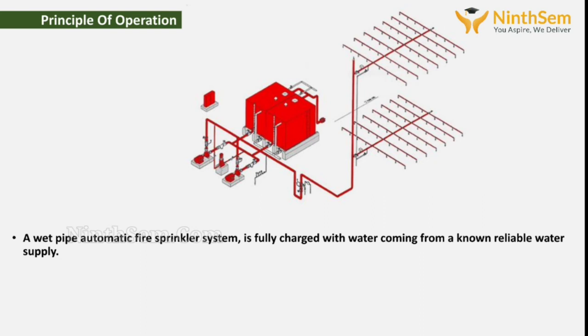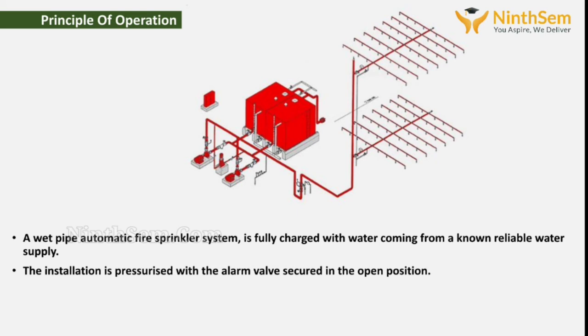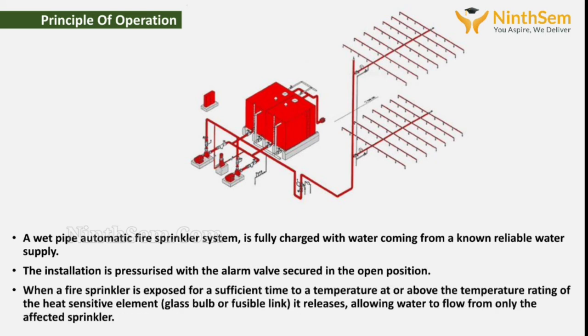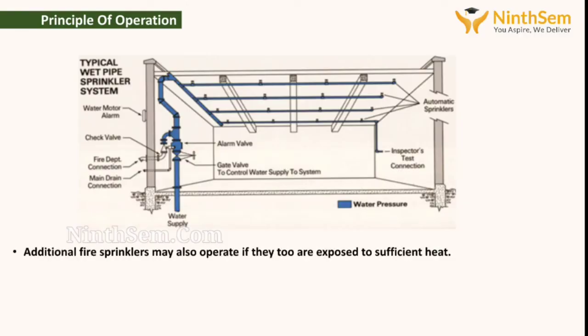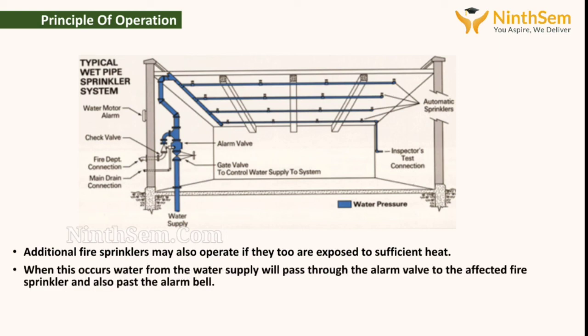So normally a wet pipe automatic fire sprinkler system is fully charged with water coming from a reliable water supply. Then the installation is pressurized with the alarm valve secured in the open position. When a fire sprinkler is exposed for a sufficient time to a temperature at or above the temperature rating of the heat sensitive element, that is the glass bulb or fusible link, it releases, allowing water to flow from only the affected sprinkler. Additional fire sprinklers may also operate if they too are exposed to sufficient heat. When this occurs, water from the water supply will pass through the alarm valve to the affected fire sprinkler and also past the alarm bell.